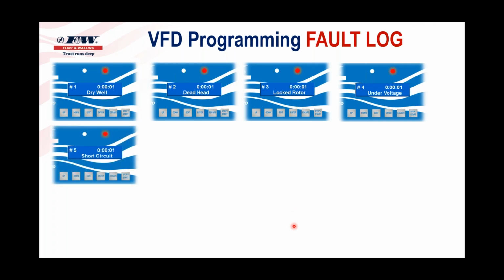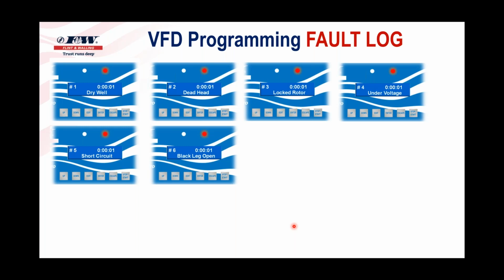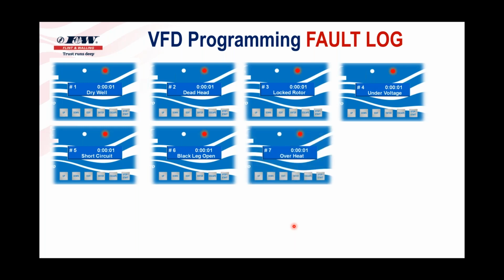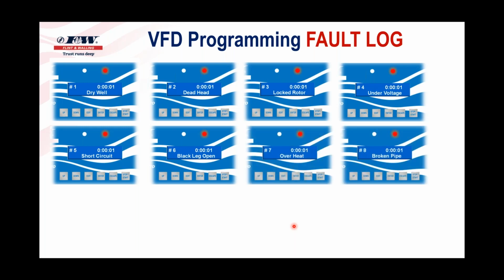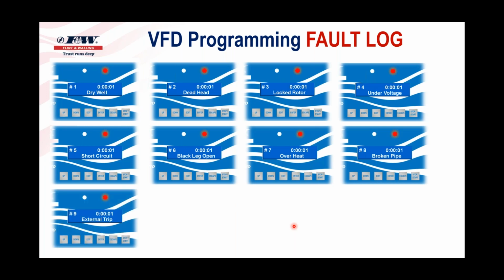There's more. Short circuit. Here's, hey, if there's a broken wire, our drive is not only going to tell you that you got a broken wire, it's going to tell you what leg is open. So it sends 3 pings down that pump cable and decides which ping didn't come back. So it can be displayed black leg open, yellow leg open, red leg open. But it's very nice. Overheat. I think that's broken pipe. That's behind my dashboard. External trip. External trip can occur. And by the way, if you ever get one of these, it's got nothing to do with the drive. It's something that is wired to the drive that is external of the drive.